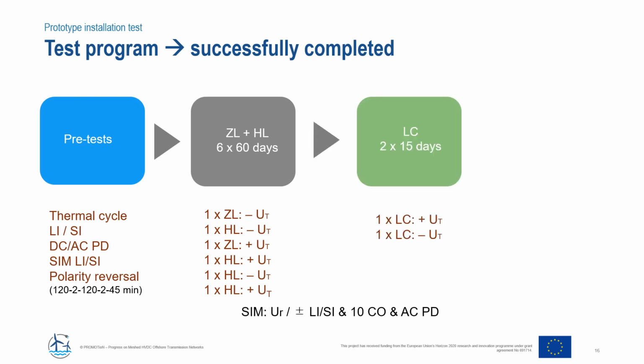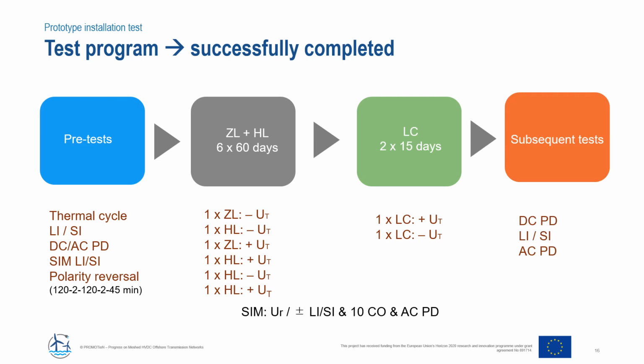And then, of course, the whole cycle has been successfully completed, because at the moment of speaking, this test has been finished, and the main test blocks are followed by a load cycle. In the load cycle, the current is varied between zero load and high load, and this has been performed in two blocks, each block lasting for 15 days, which corresponds to each polarity. So 15 days positive polarity, 15 days negative polarity, while the load current is varying between 0 and 4000 amps.